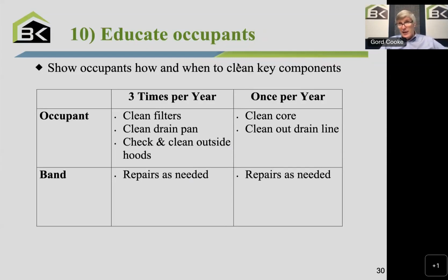That cleaning of the fans, the toothbrush and the fan, that's no more than once a year, and it's probably only every 5 to 7 years. Typically, they just don't get dirty. So that's kind of where we like to be. And we'll finish off with just a bit of a summary.